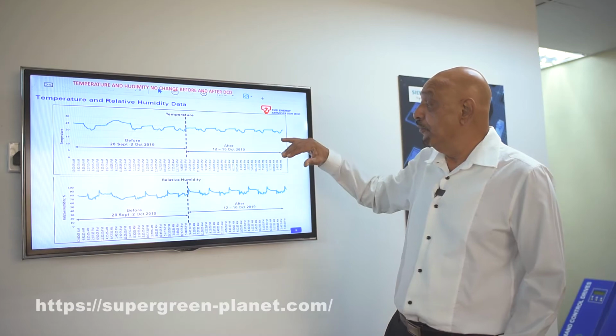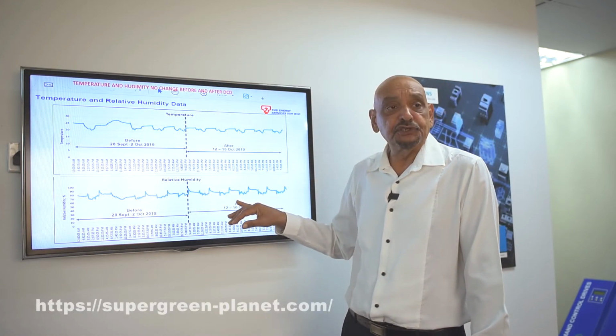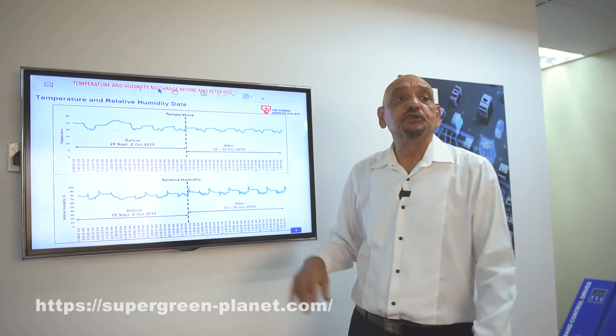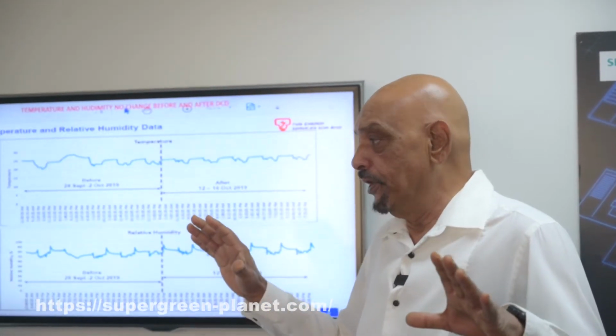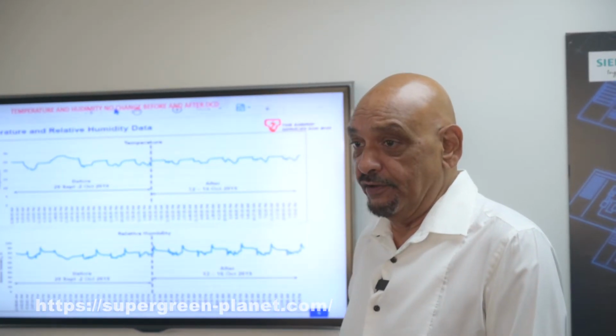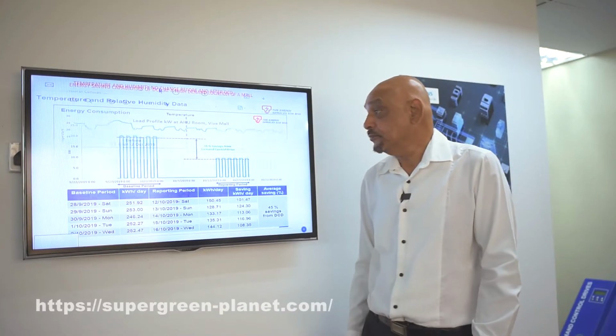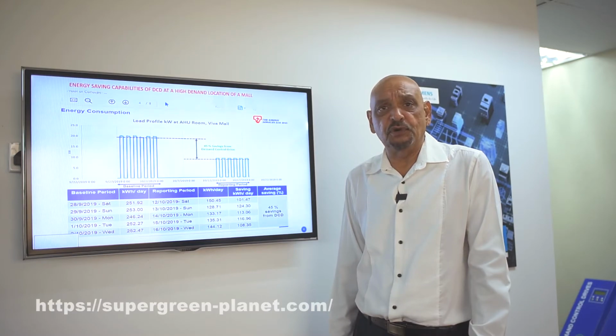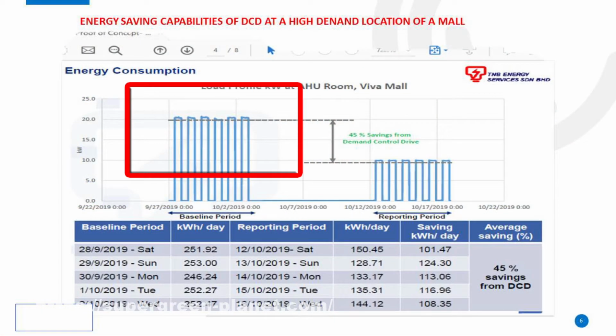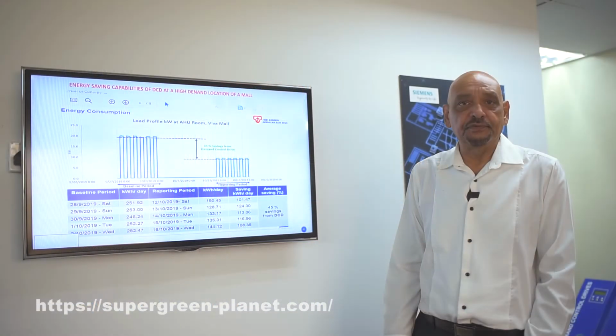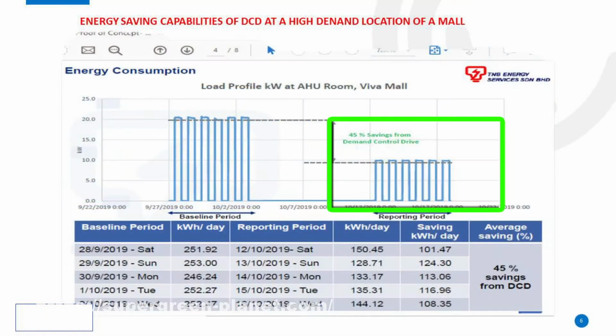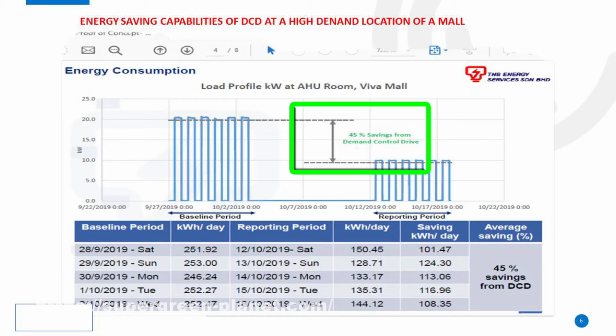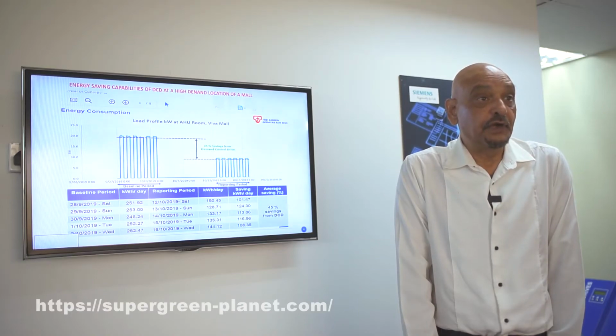Similarly, we would find the relative humidity, there was no change. The temperature profile within the environment was more stable. It was more stable because with demand control drives, you got better airflow, smoother airflow, and you have got a slightly cooler air than what it used to be. As far as the electricity consumption was concerned, this was the baseline before demand control drives were installed, and after the demand control drive, this is the saving period, and you have got a 45% reduction in energy consumption in a very high demand location without loss of efficiency.